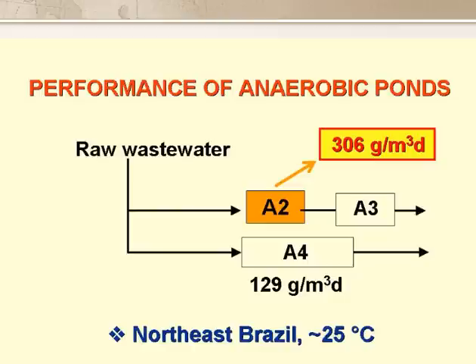This is some work we did with anaerobic ponds in northeast Brazil some 25 years ago — in fact it was the first work done on anaerobic ponds anywhere in the country. We had two anaerobic ponds in series, coded A2 and A3, and in parallel with these was another anaerobic pond, A4. The pond temperature was around 25 degrees throughout the year, and the loading on A2 was just over 300 g/m³/day, and on A4 just under 130 g/m³/day.